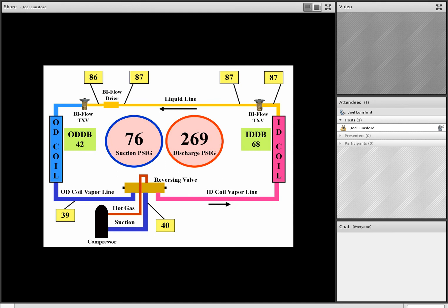It's acting like an evaporator, so that coil is starved or empty. We see that we have high superheat on the outdoor cold coil, and the outdoor coil superheat was 21 degrees. That's very, very high. It should be anywhere between about 4 or 5 as high as 15 based on the temperature outside. But we see we have 21 degree superheat, so the outdoor coil is starved. We've got 2 degrees of subcooling on the indoor coil. The indoor coil is starved.